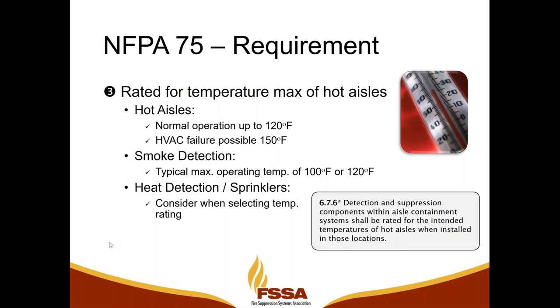But now, as we've gotten more sophisticated in data center operation, we are increasing the inlet air temperature, meaning the cold air temperature coming into the face of the servers, which is correspondingly increasing the hot air temperature. And so we see many hot aisles operating at around 120 degrees Fahrenheit. But if the HVAC would fail and the IT equipment would continue to operate, we are seeing buildups within a couple minutes of hot aisle temperatures up to 150 degrees.